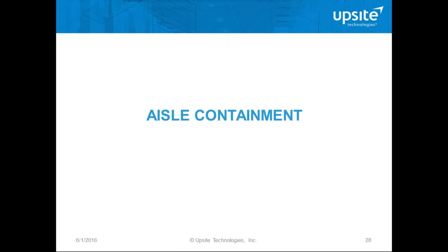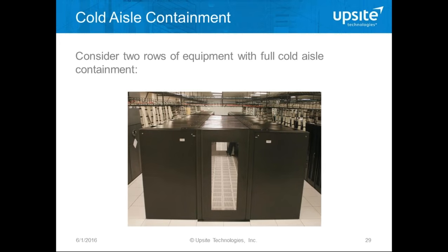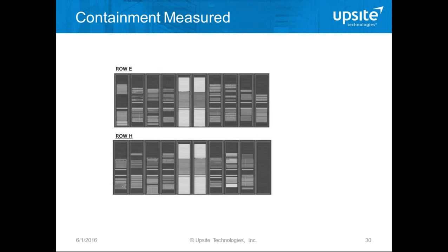Common practice nowadays is to install aisle containment — a really important feature of airflow management. Typically people install contained aisles with doors and a roof. Let's look at two rows in a single aisle in a simulation. In this data center, rows E and H have a variety of IT equipment installed, and this is a view of the front faces of the two rows in that aisle containment scenario.